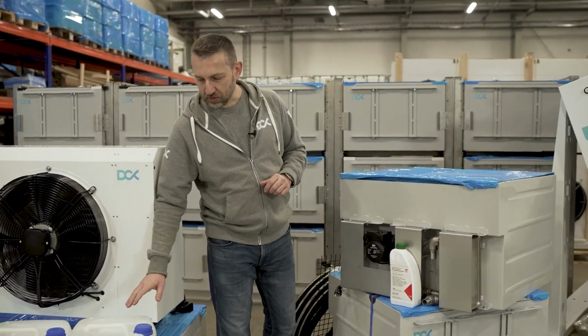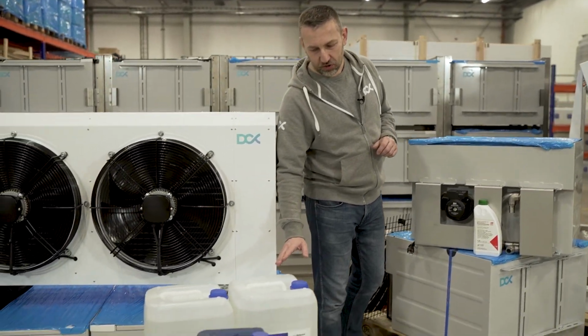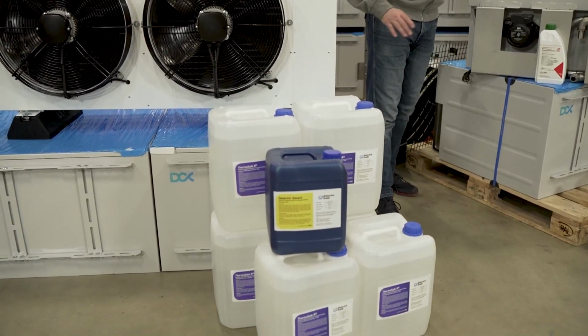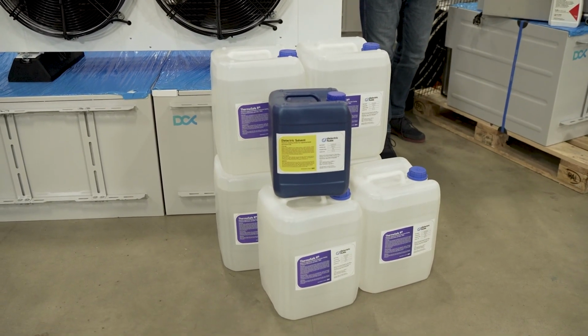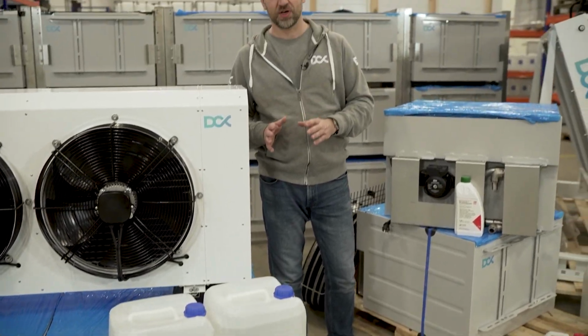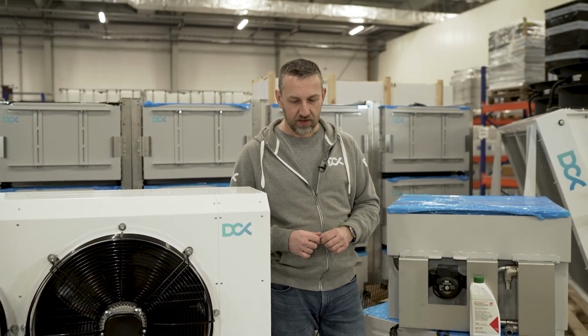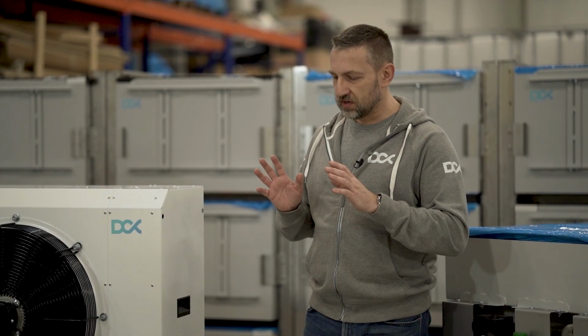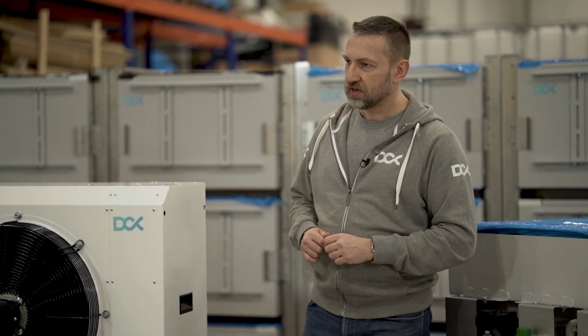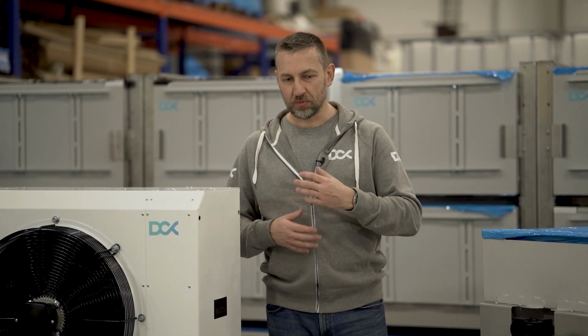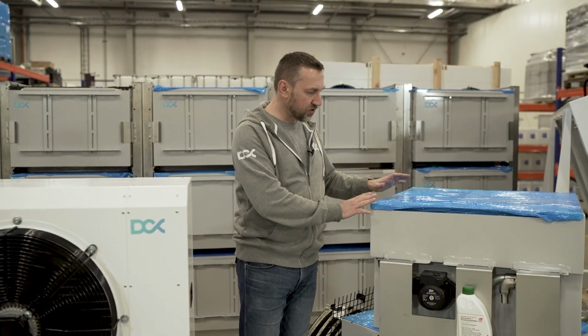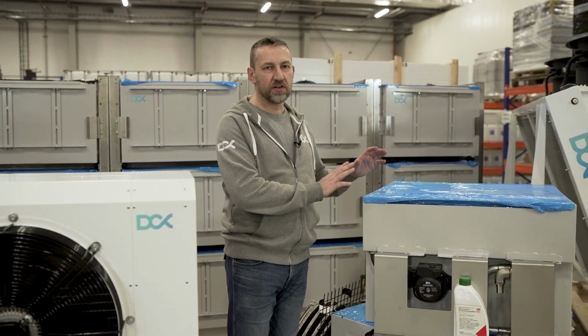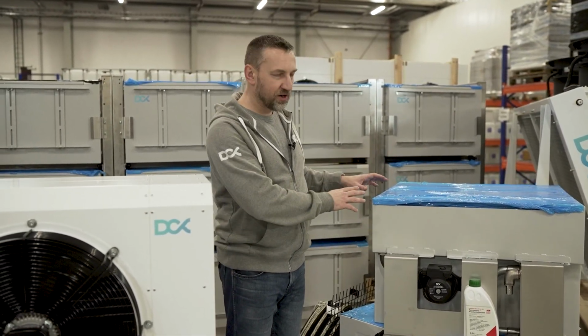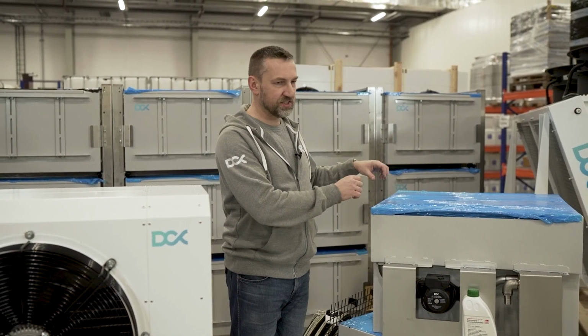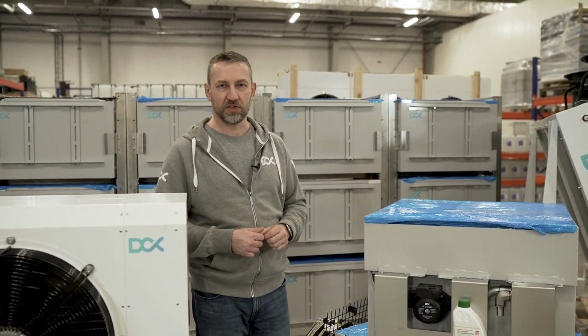As you may know, we are also usually shipping 250 liters of the ThermaSafe, the most affordable and actually the best. I don't want to brag, but this is the best dielectric fluid you can get. It's a fully synthetic fluid designed for cooling electronic components, especially taking into account the complexities of crypto mining hardware. The enclosure actually takes approximately 230 liters when fully loaded with miners, since they displace the fluid, but we're shipping 250 just to be on the safe side.